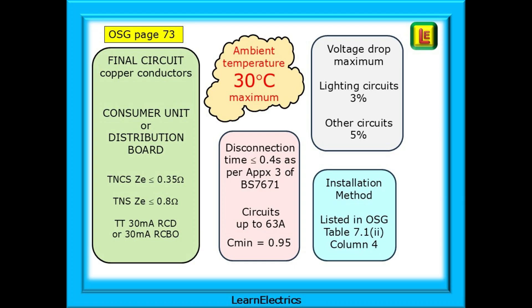and TT systems with 30mA RCDs or RCBOs. The ambient air temperature is assumed to not exceed 30 degrees Celsius - the cooler the better. Disconnection times should not be more than 0.4 seconds for circuits up to 63 amps with a C-min of 0.95. Voltage drop has a maximum of 3% of nominal voltage for lighting circuits and a maximum of 5% for all other circuits. Finally, the installation methods should be as listed in Table 7.1(ii) in the On-Site Guide.